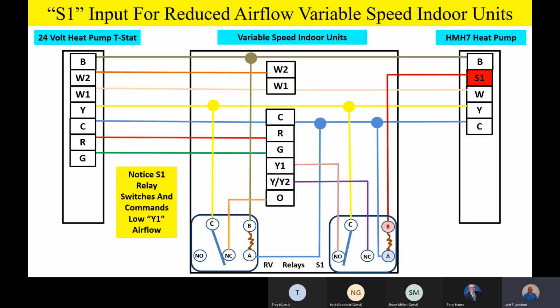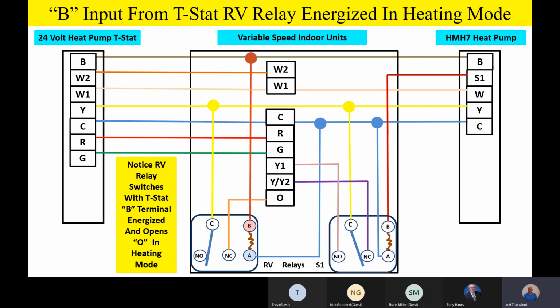So just like before, when we energize S1 outside for reduced airflow, we click that S1 relay inside. The contacts shift to low speed airflow. So that's the relay logic for the reduced airflow on our variable speed product. Now watch this. On the RV relay, look what happened. Notice the RV relay switches with a thermostat B terminal energized. So anytime we call for heating on the heat pump, we energize the B terminal, we switch that RV relay, and we break the circuit to the O terminal.